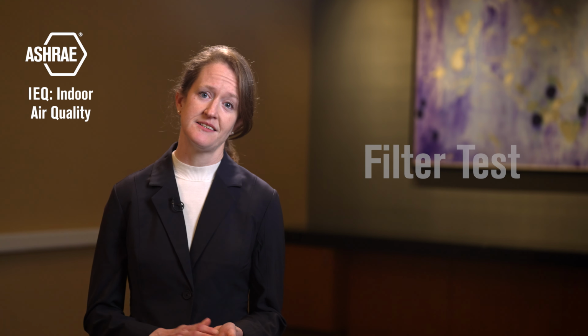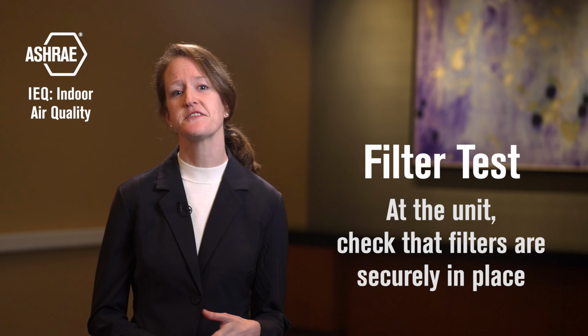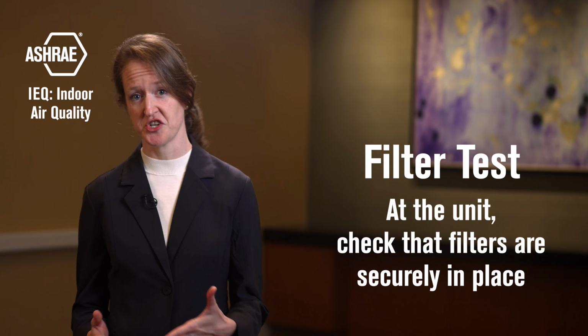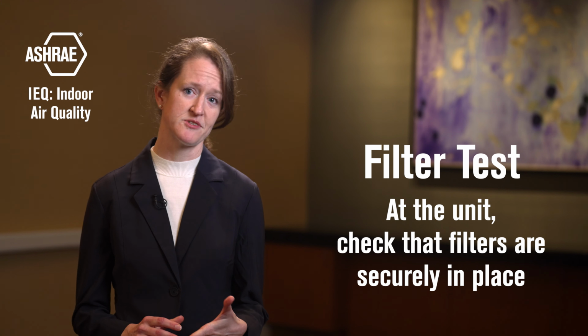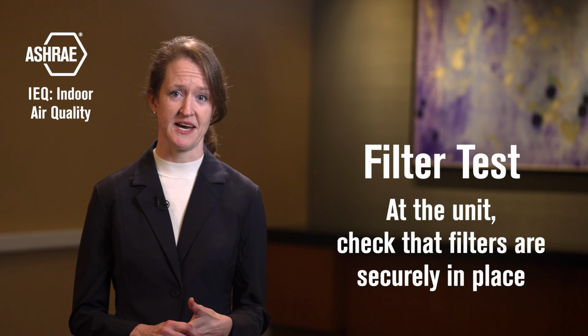Now the filter test. At the unit, check if the filters are in good condition and securely in place, without any gaps around the edges that could let air bypass the filter. Tape can be helpful here. If they're overloaded with dust or collapse, a filter change is overdue. Once you're confident air is going through the filter and not around it, you can think about upgrading filters.